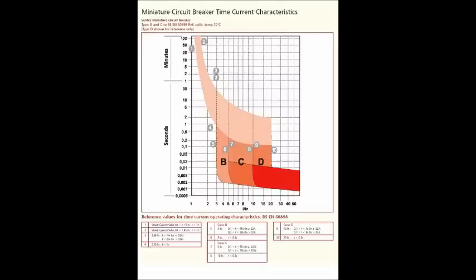Back to this breaker. Now that we know what DC means, we look down here and it says C-16. The 16 is the amps at which the breaker blows. But the C is really important — the C is the curve at which a breaker blows. Most people never think about the curve at which a breaker blows. And this is really important, especially if you're on boats, alternative power, off the grid, or on generators.